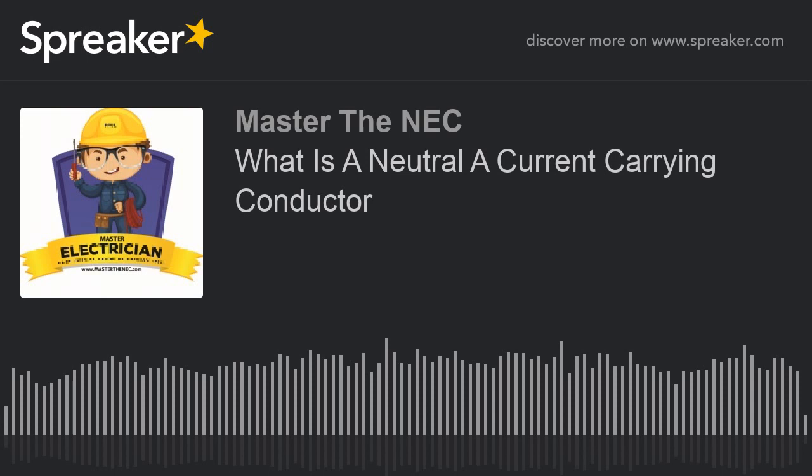Okay? So if I have 100 amperes on leg A and I have 50 amperes on leg B, then the only thing that we're going to see on the neutral is the unbalanced current, which would be 50 amperes, because I've got 100 on A and 50 on B. So the return current is going to be 50 amperes on the neutral.